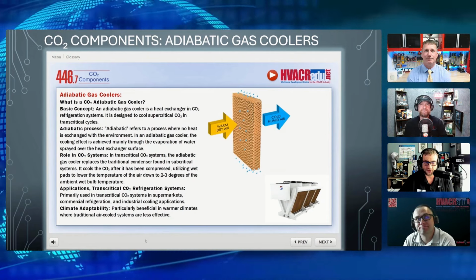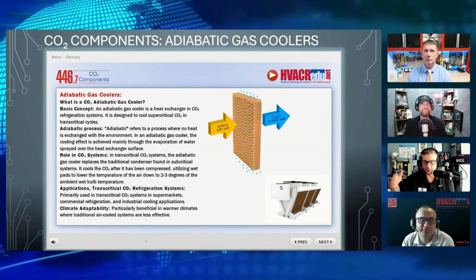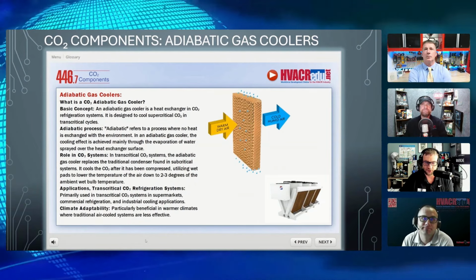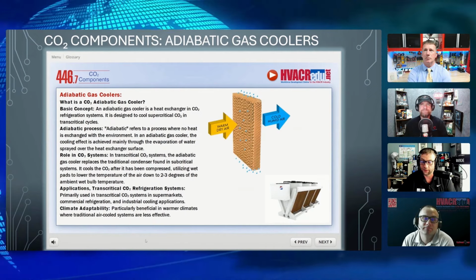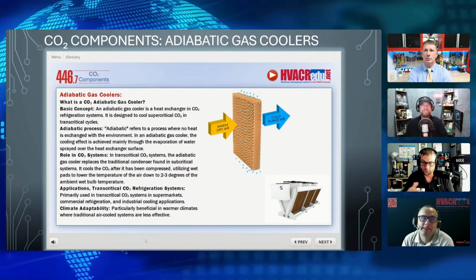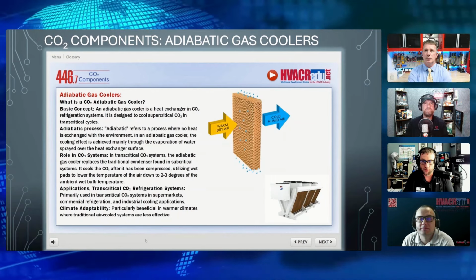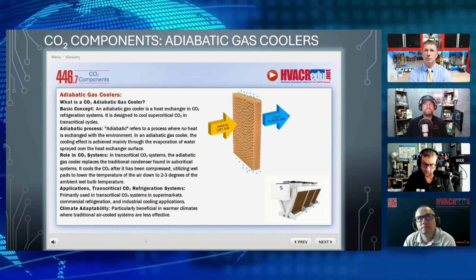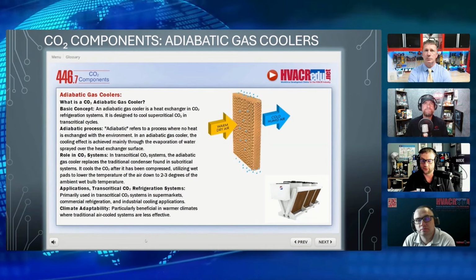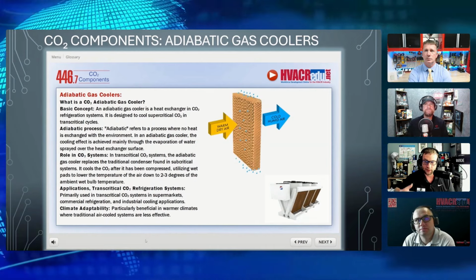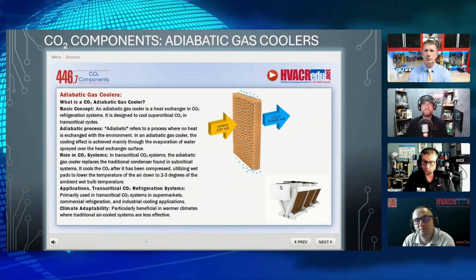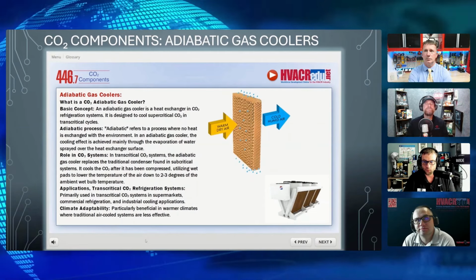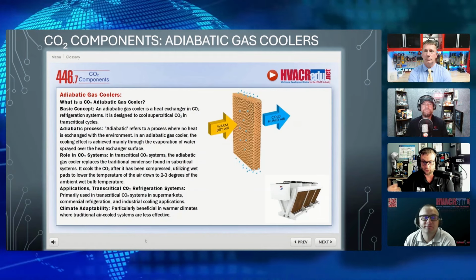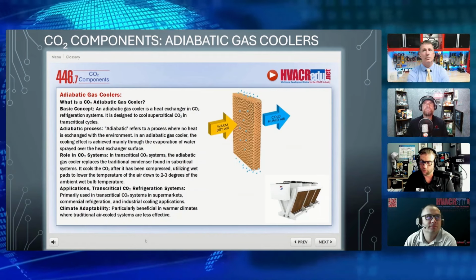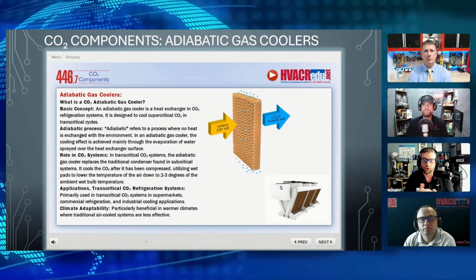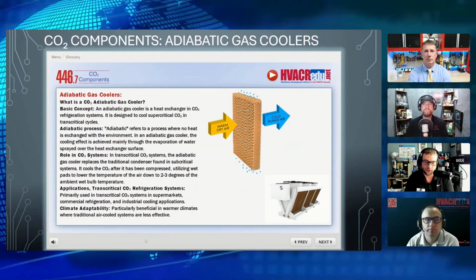That's essentially what we're doing with adiabatics, right? We're dripping water across there to get a lower wet bulb temperature and more capacity out of the air, in order to keep a system running subcritical as long as humanly possible. Like I had stated before, it takes more energy once we get into that transcritical state. We produce a lot more flash gas, so we need to turn on more compressors in order to mitigate that pressure. So in order not to do that, we have the adiabatics to mitigate running into that transcritical state as much as humanly possible.